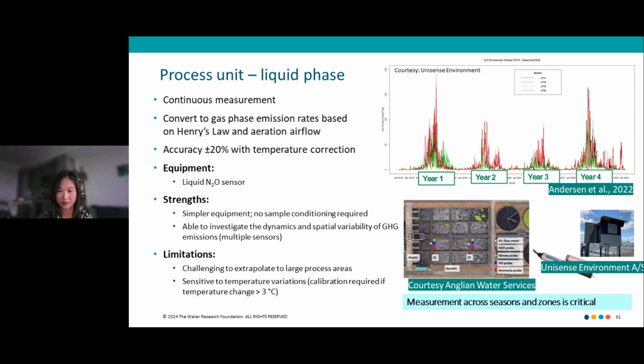So calibration is required if your wastewater temperature changes by more than ±3 degrees Celsius. So for example, where I am in Southern Ontario, in spring season, we do see snow melt. So there's a pretty significant temperature drop in that period. So you do need to keep an eye on your sensor and do the calibration as needed.